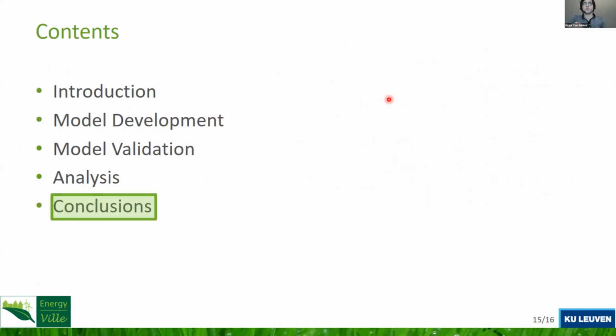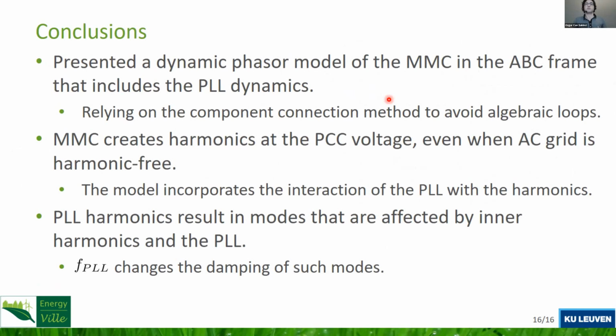Now moving on to the conclusions of this paper. In this work, we presented the development of a dynamic phasor model of the modular multi-level converter in the stationary ABC frame, including the PLL dynamics. The model was developed relying on the component connection method to avoid algebraic loops in the development. We saw that the MMC creates harmonics at the voltage of the point of common coupling, even when the AC grid is free from harmonics.